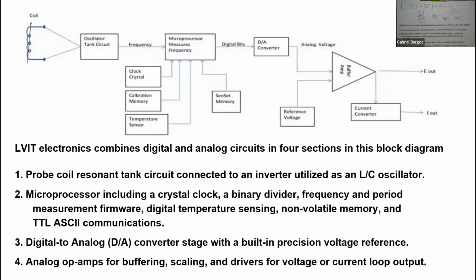Well, the thing about LVITs is that with many of them, you can do field programming to change the scale. So if you're putting it into a PLC, you might say it doesn't matter much, since you could make the gain adjustment in the PLC. But if you're using it in a simple apparatus, you can adjust the output yourself. I also have the availability of voltage outputs or a current loop output, so I can use whichever one I want depending on my application, and I can adjust it through ASCII commands.